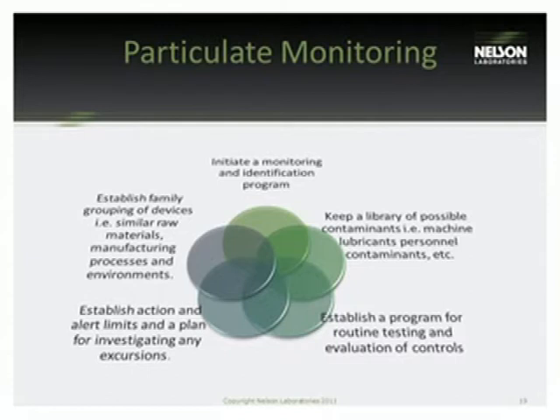Here at Nelson, we've initiated a monitoring program in our particulate lab and other parts of our laboratory. As a manufacturer, it's not a bad idea to also establish families of devices or raw materials and where those are located, establishing action plans and alert limits for investigations, and keeping a library of contaminants and lubricants, things of that nature regarding equipment. We've often found this to be significant. We've found oils and different manufacturing contaminants that are specific to the machinery used on some devices, and during investigations have come back to find that there may be some equipment contributing particulate matter, whether in the form of actual solid particulate matter or in some cases oils or other lubricants that don't necessarily qualify as a particulate but can sometimes cause false positives with our particle counter.